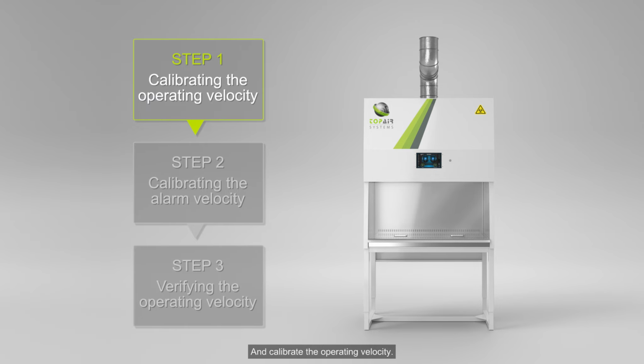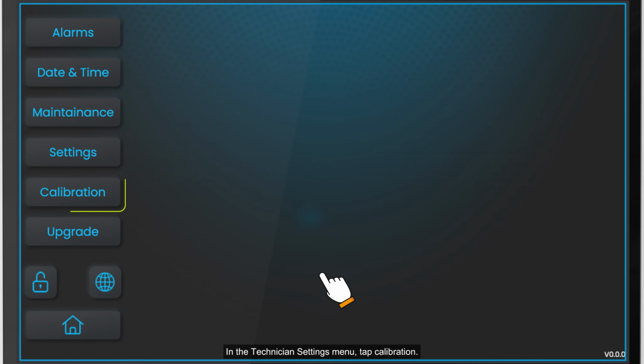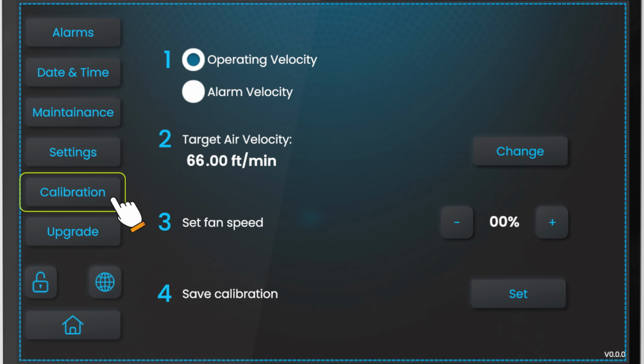First, tap the fan button to turn on the blower. On the home screen, tap the Settings button. Tap the Lock button and enter the passcode. Then tap OK. In the Technician Settings menu, tap Calibration. To calibrate the operating velocity, you must first calibrate the downflow velocity and then the inflow velocity.